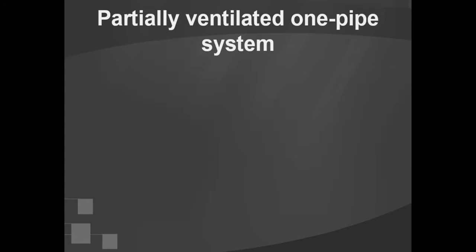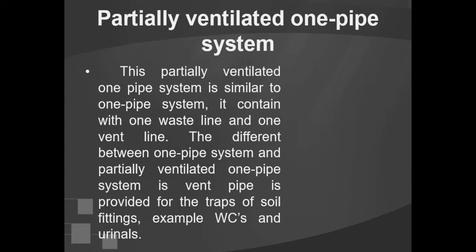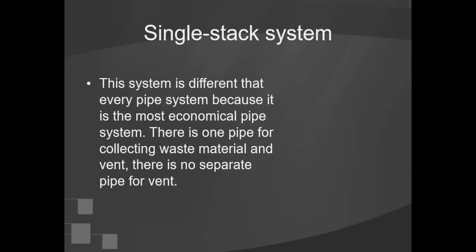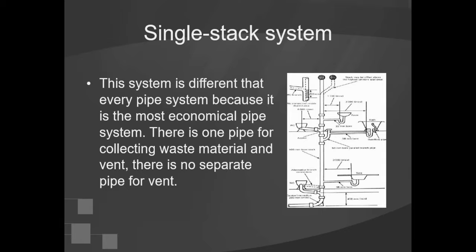The partially ventilated one pipe system is similar to the one pipe system, containing one waste line and one vent line. The difference is that a vent pipe is provided for the traps of soil fittings such as WCs and urinals. The single stack system is different from every other pipe system because it is the most economical. There is one pipe for collecting waste material and venting — there is no separate pipe for vent.